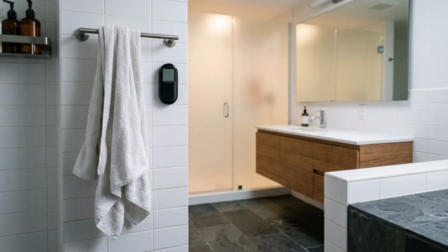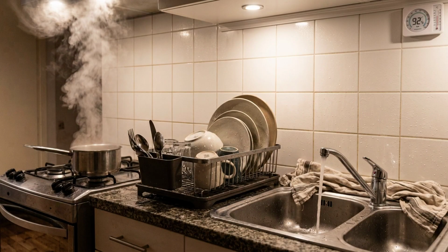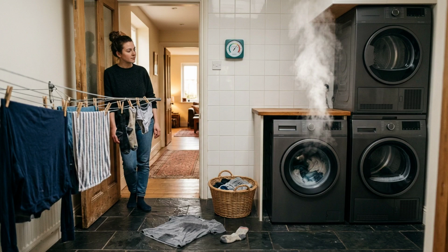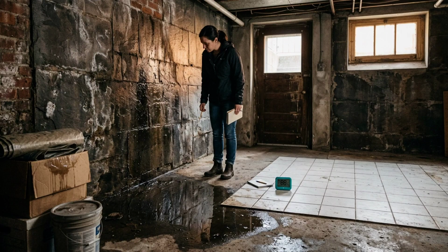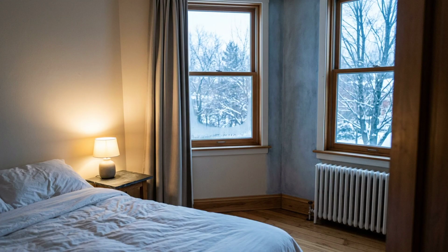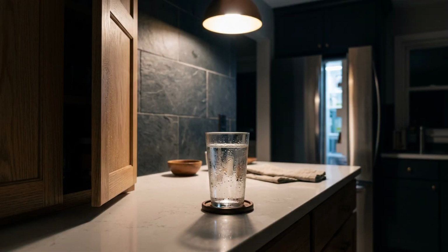A shower may push bathroom humidity upward. Effective exhaust should remove that concentrated moisture and the reading should move back toward its earlier level. Cooking, dishwashing, wet laundry, and a room full of people can produce their own temporary rises. An all-day plateau is different. So is a basement reading that rises after rain, a closet that stays higher than the room outside it, or a bedroom that climbs every night and does not recover. Do not force all of those patterns into one explanation. They point toward different sources and different checks.